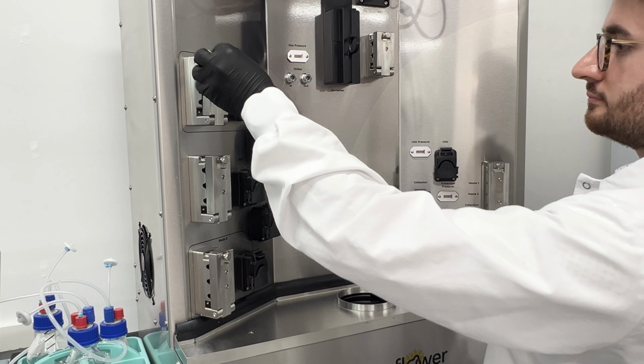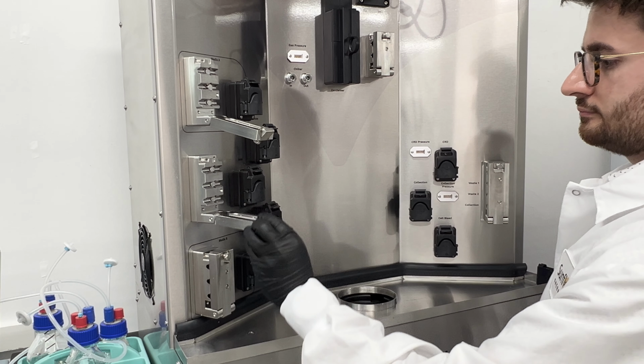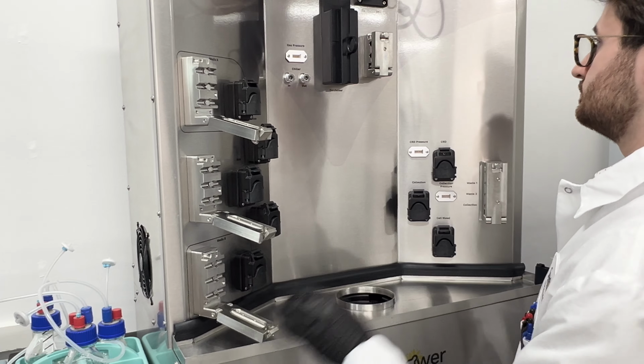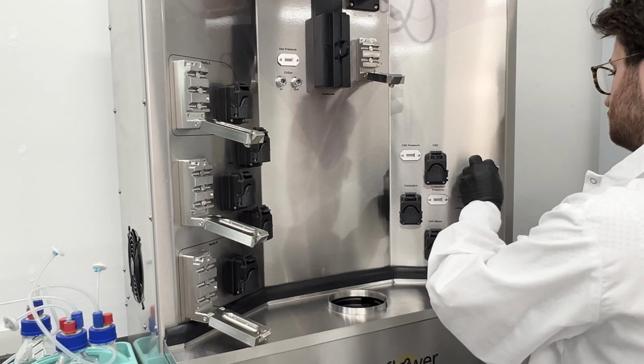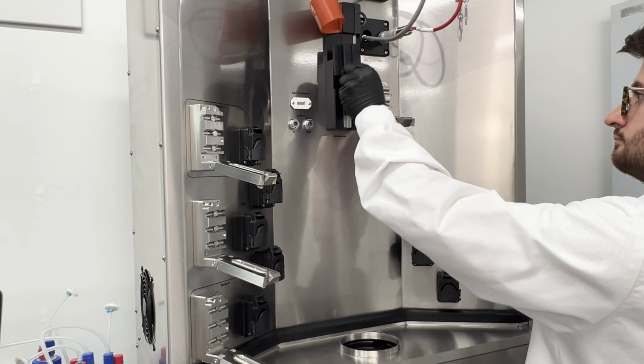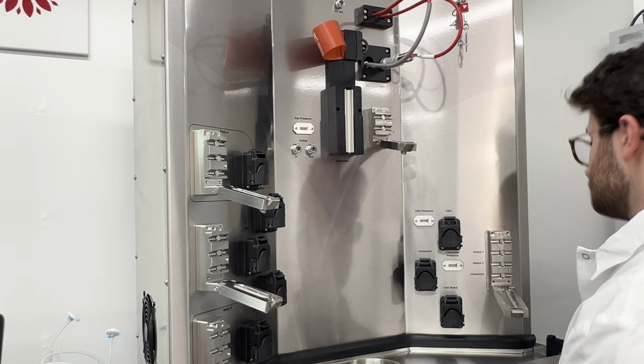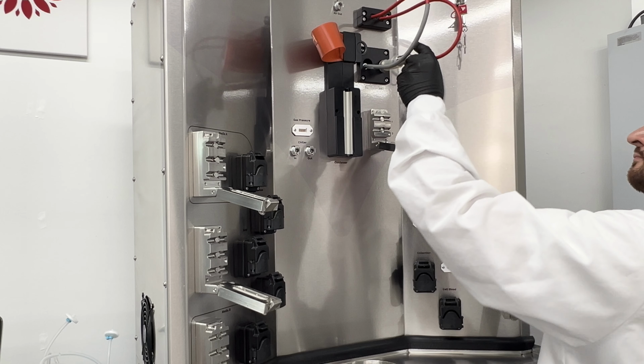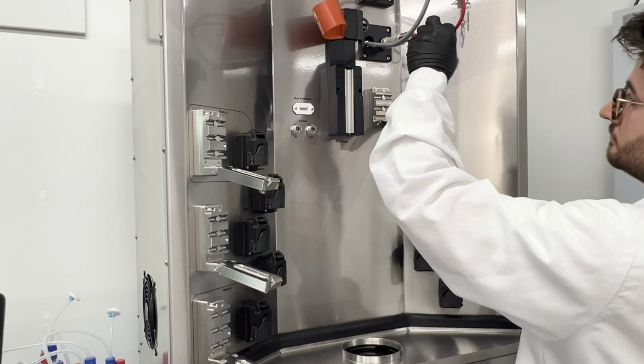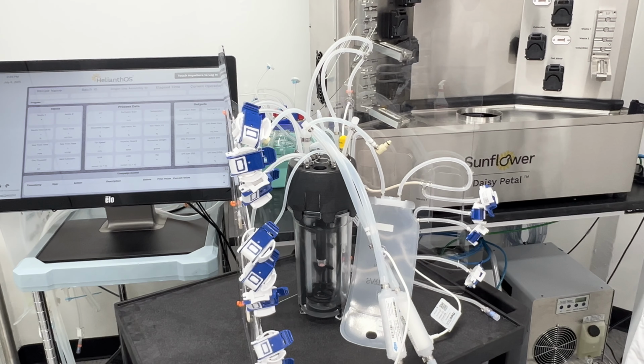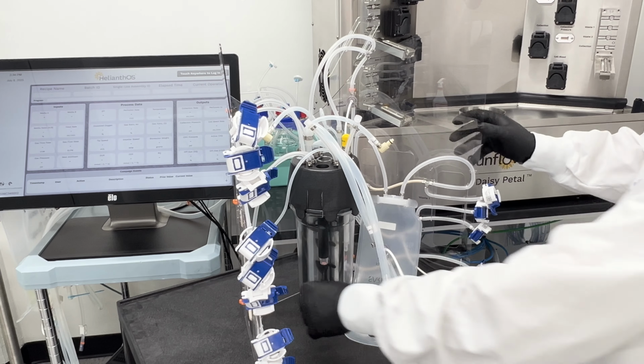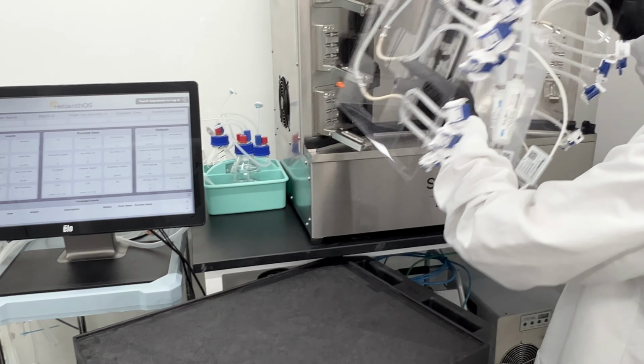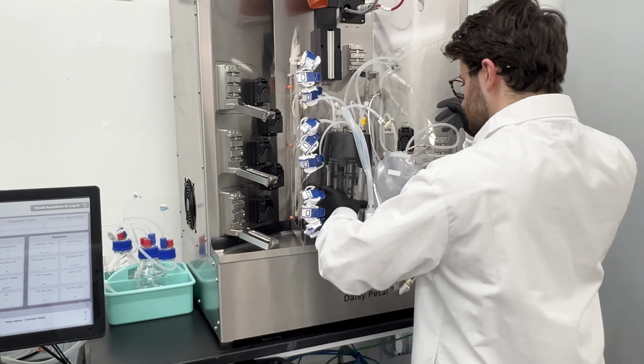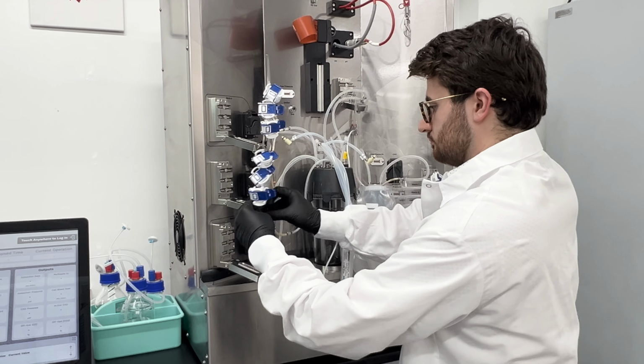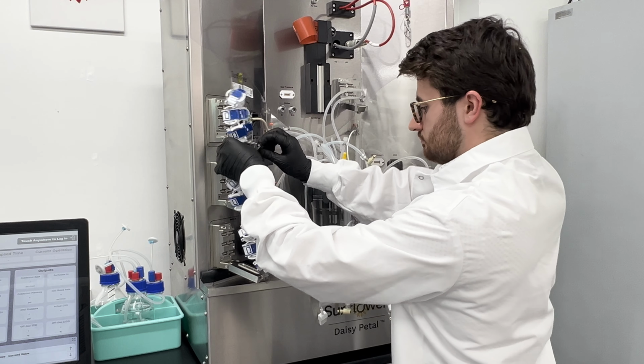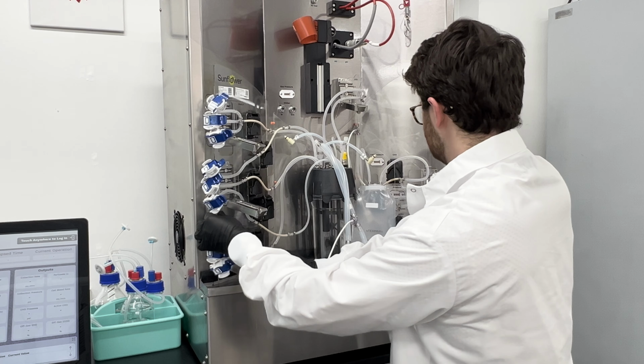To begin the SUA installation process, we need to prepare the Daisy Petal hardware. First, we'll open all the valve gates by loosening the thumb screw and pressing down on the lever. Then, we'll remove the magnetic condenser cover and make sure that the DO and pH cable connectors are tucked away into the respective holders. I've already removed the single-use assembly from its packaging, so we can simply pick it up, supporting the bioreactor from the bottom, and place it onto the Daisy Petal system. Fit the open doors of the valve gates through the corresponding cutouts in the loom to fully unfold the SUA.